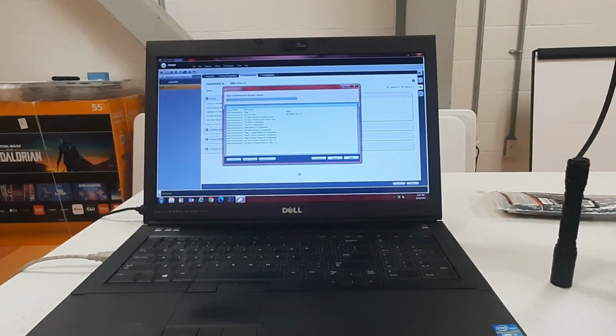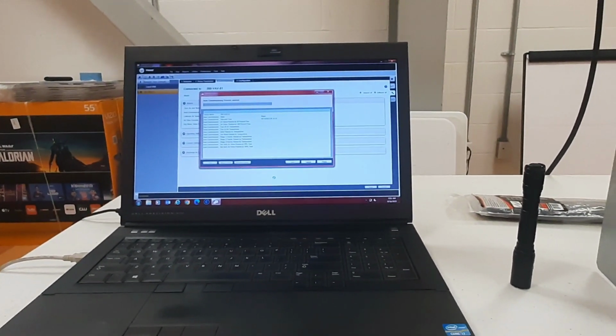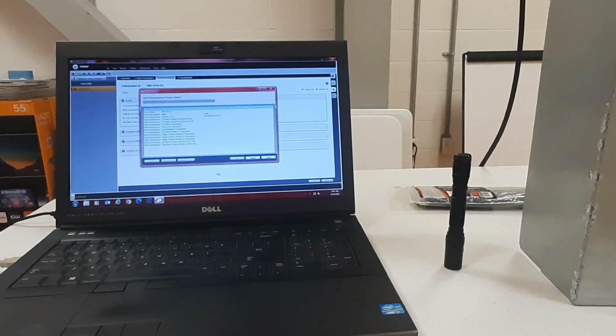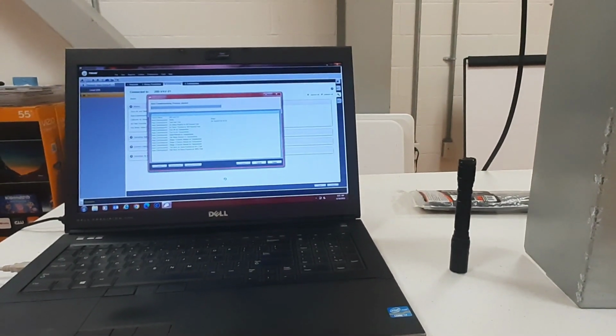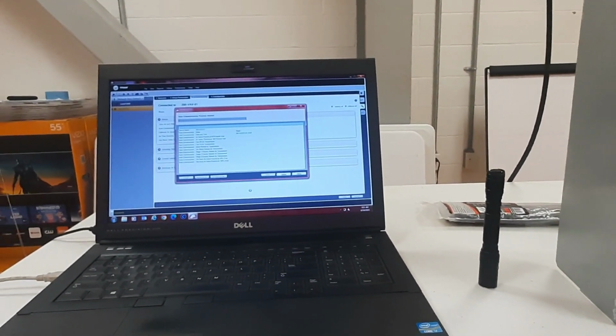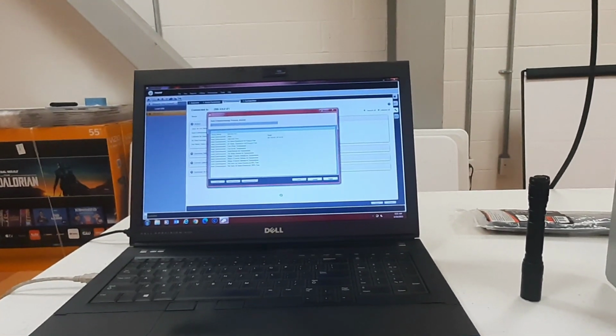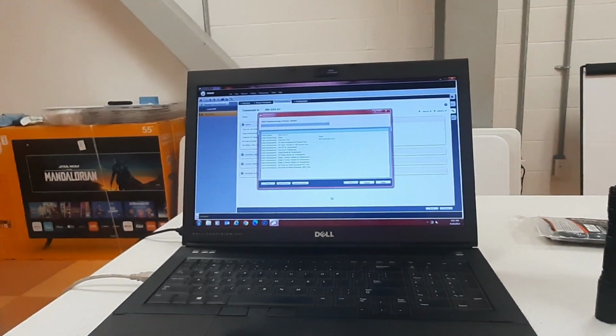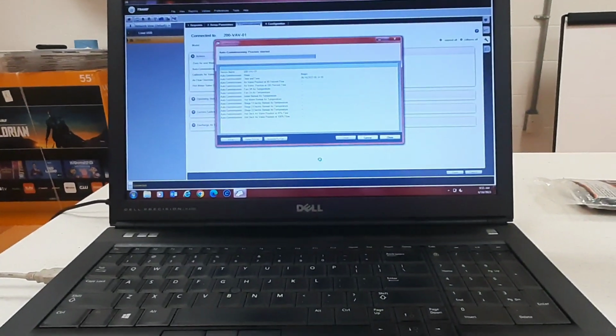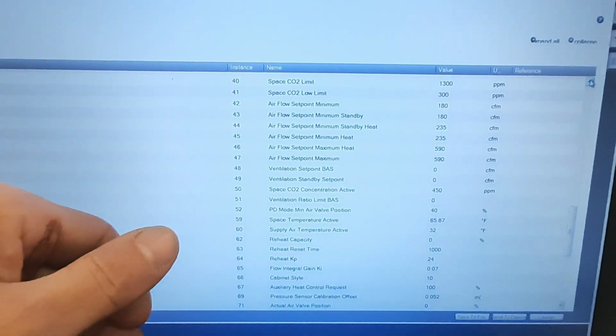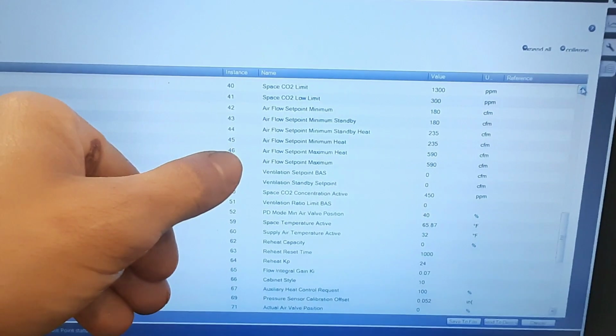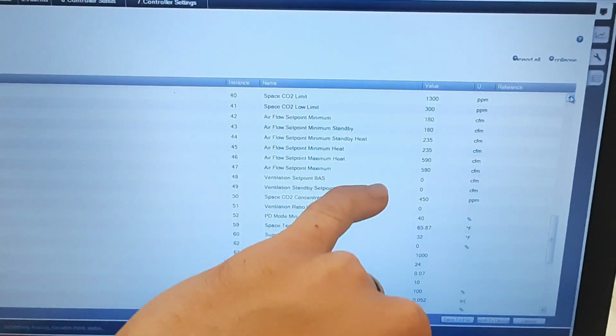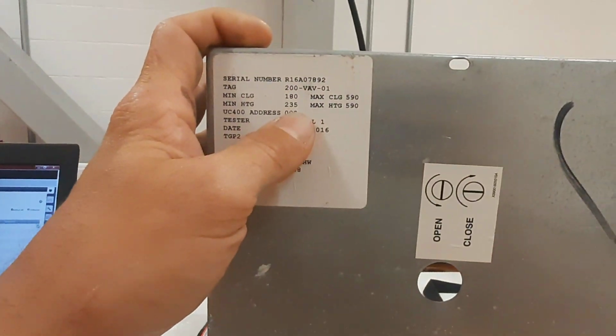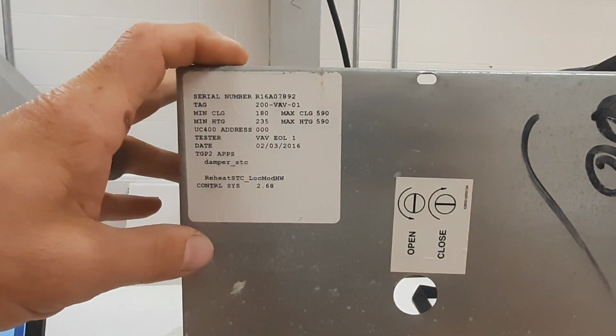I don't know why it's responded from when I was plugged into the SC. I can always go plug in there if I need to, but it's responded to me before because I can see it, and I've been able to at least close the damper, because that's what I did initially when they had the condensation issues on the other side. So I can see here my set points, maximum heat were 590, 235, 180. All that's been set. So they must have set that up initially.